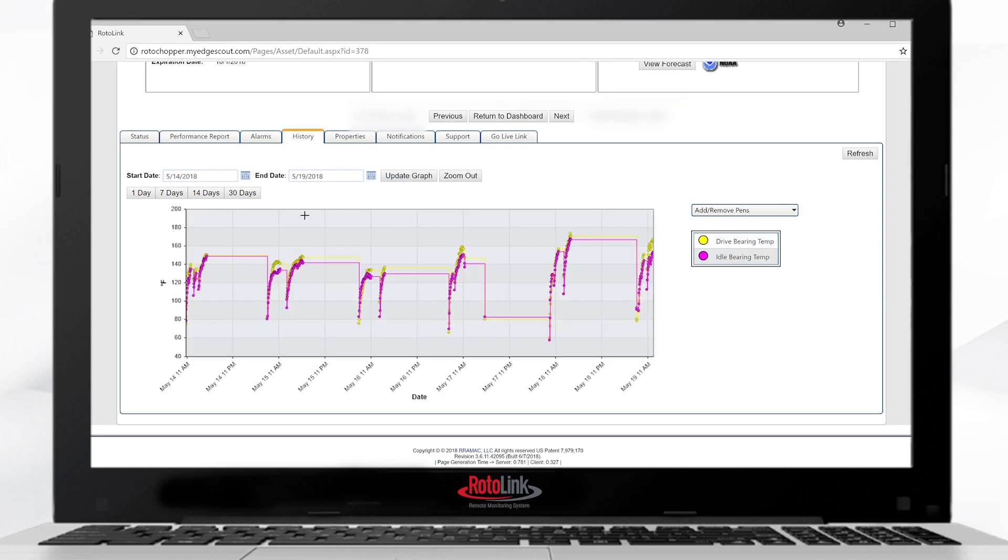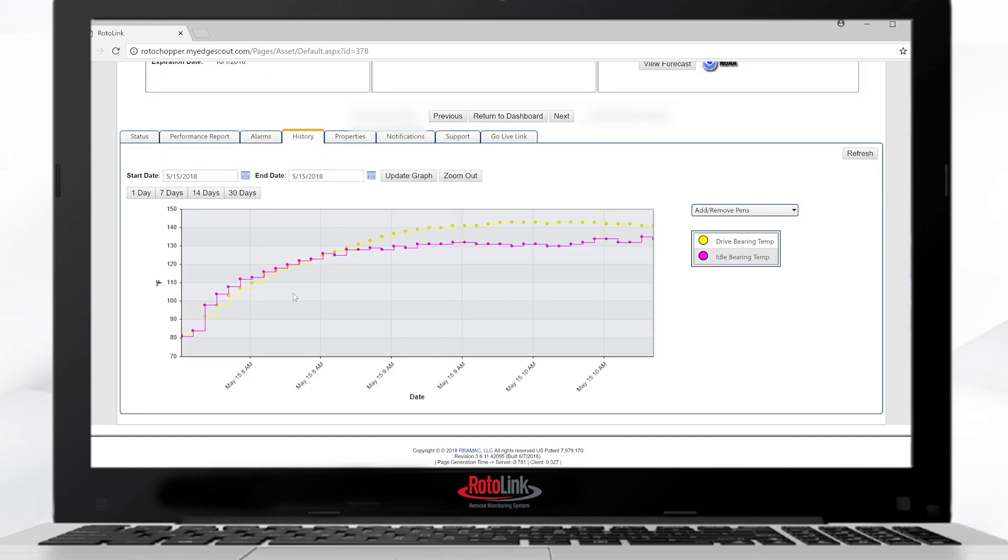We can also track bearing temperatures. Each daily sample, each one of these graphs is showing the daily run of the bearing temperatures. We can see the difference between the drive side and the idle side bearings. If we have any kind of anomaly or it doesn't look quite right, we can zoom right into that graph and see exactly what the bearing temperatures are doing. It's taking a bearing sample every minute and the data is sent to the rotolink website every five minutes. It's updating every five minutes.